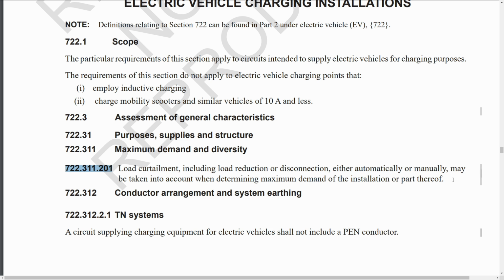So if you program it in, say, a thing which supplied 4 different vehicles, you could program it so that the total load in the installation can only be a maximum of, say, 80 amps or something. Then it has a monitoring device on the supply conductors, and therefore when you plug in one or more vehicles, the total actual load or amount of power that can be provided to those vehicles will be automatically adjusted so that the load on the installation does not go above the set value.